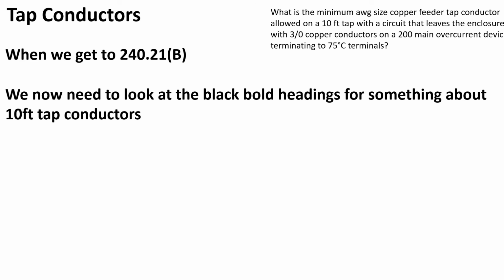And then part 4 is what we're looking for in our question. For field installations, if the tap conductor leaves the enclosure or vault in which the tap is made, the ampacity of the tap conductor is not less than 1/10 of the rating of the overcurrent device protecting the feeder conductors. Okay, so in this case, we're going to use part 4 because our question states that the conductors leave the enclosure, and it lets us know that it is on a 200 amp main overcurrent device. So in this case, regardless of the load, even if you have a 2 amp load, you have to size this conductor if it leaves the enclosure at a minimum of 1/10 of the overcurrent device that you're tapping from.